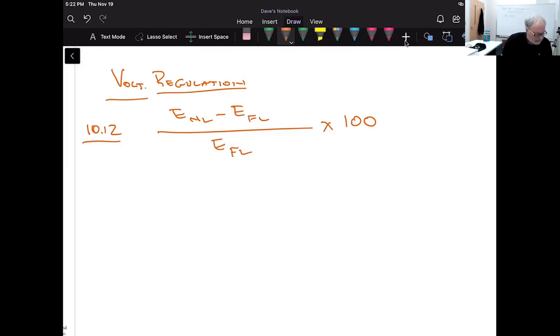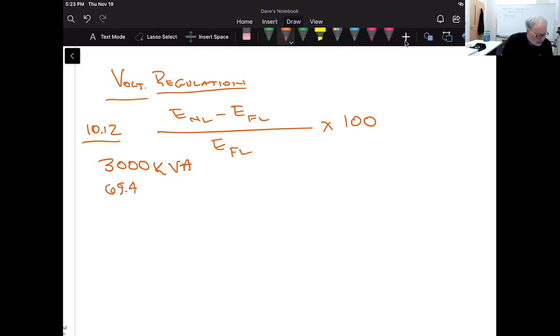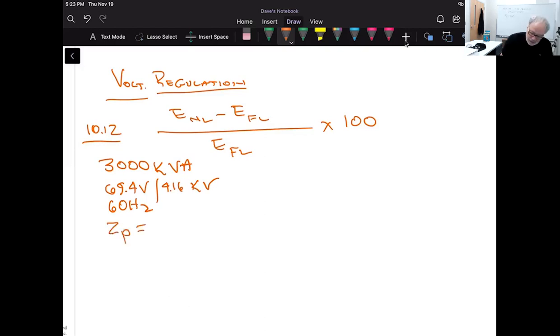Let's work through problem 10.12. We have a single-phase transformer rated at 3000 kVA, with a 69.4 kV primary and a 4.16 kV secondary, operating at 60 Hz. The total impedance Z_p referred to the primary side equals 127 ohms. First, we're asked to find the primary and secondary rated currents.